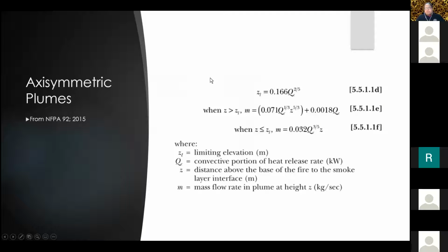If you're going for axisymmetric plumes, you use this formula. ZL is the limiting elevation, QC is the convective portion of the release rate, Q is your fire size, then the distance above the base of fire to the smoke layer interface, and the mass flow rate in the plume at height.